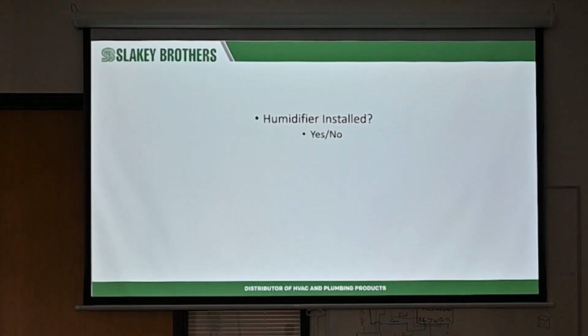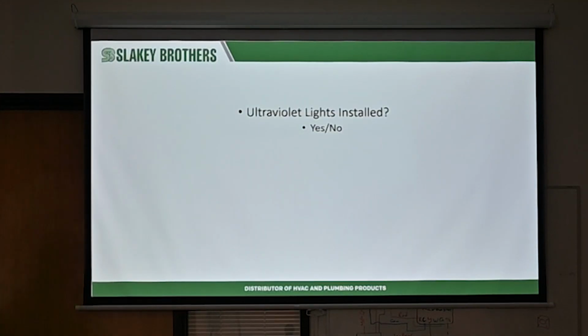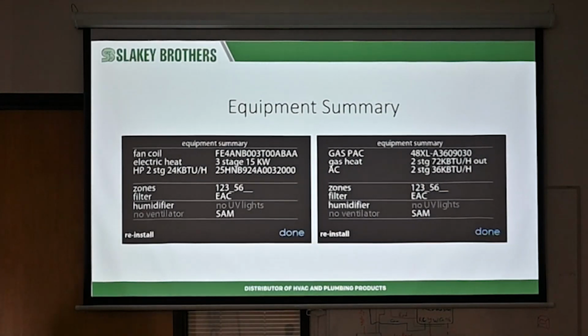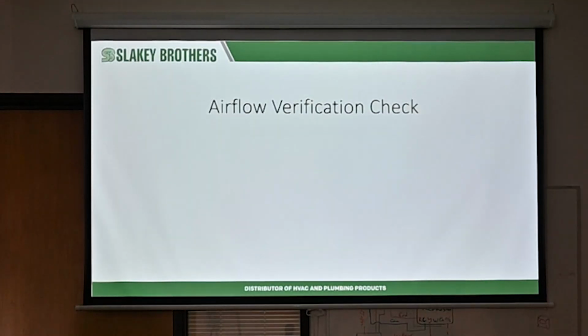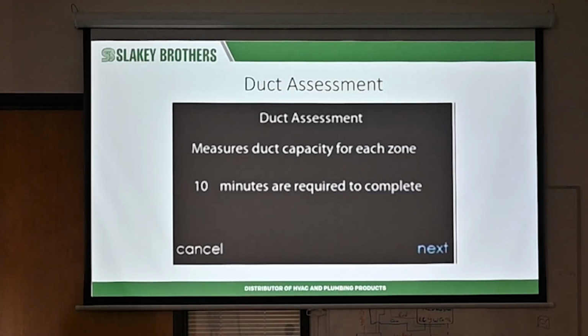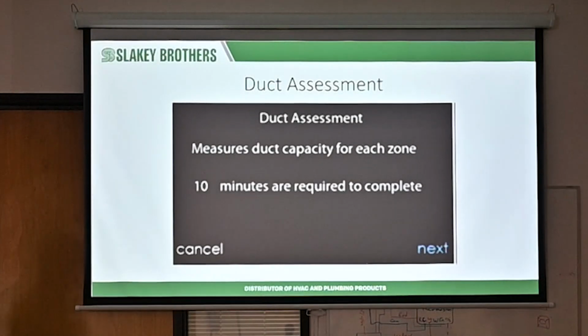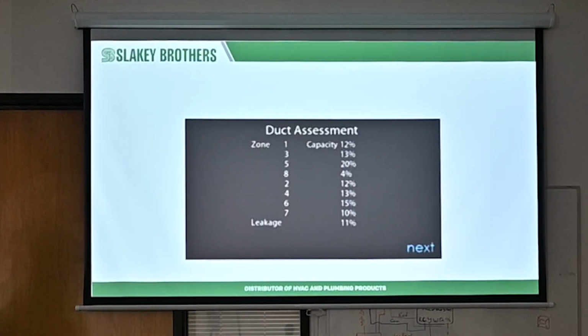You're going to tell it what kind of filter, whether a humidifier is installed or not, UV lights, and then it just tells you a little bit of equipment summary. Then it does its airflow check and duct assessment. If it's zoned, it's going to be turning on and off all these zones. So if you do have 8 zones, for instance, it's going to take its time to do all of that. But you just hit the next button, and once it's all done, it tells you how much each one can handle.